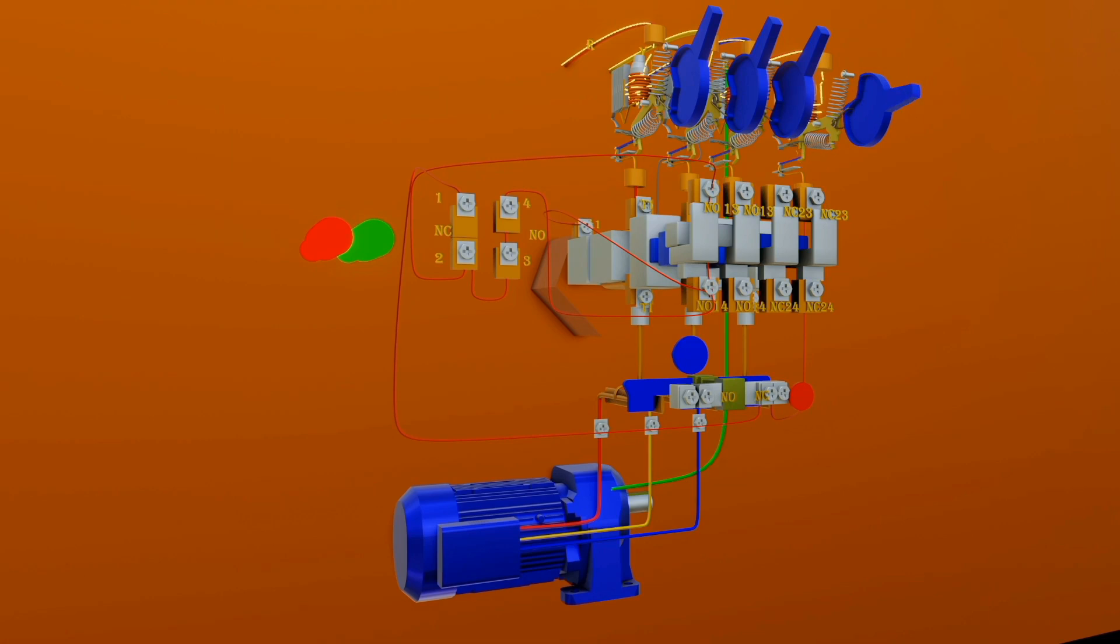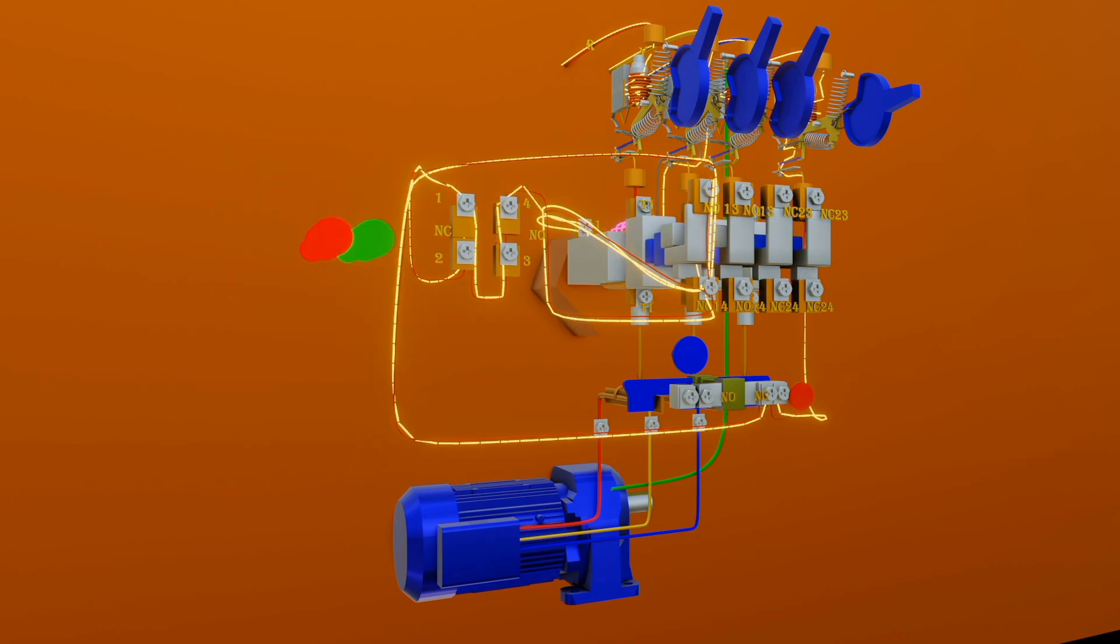For example, we have three-phase power supply connected to the power terminals of the contactors, then through the overload relay. In overload relay, the input power terminal and output power terminal is the same, nowhere is separated. Contactors only contain separated power contacts and therefore control circuit being connected to the overload relay first gives us an easier way to turn off power.